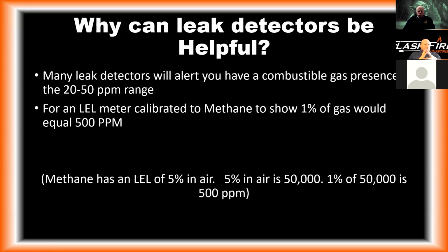Many leak detectors will alert you that you have combustible gas in the 20 to 50 parts per million range. And so I kind of go back on this. I could have put this slide earlier, but we really didn't talk much about LEL yet, so I wanted to do that before I threw this at you. So for an LEL meter calibrated to methane, to show 1% of gas would equal about 500 parts per million. Remember, methane has an LEL of 5% in air. 5% in air is 50,000. So 1% of 50,000 is 500 parts per million. I don't ever need you to do that math again.